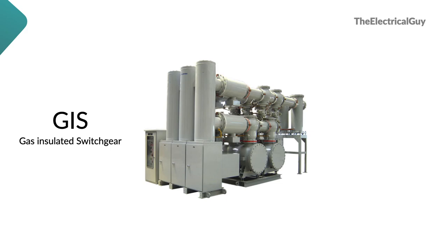There are different compartments given. The circuit breaker will have a separate compartment. The current transformer will have a separate compartment. The voltage transformer will have a separate compartment. And everything is insulated by SF6 gas. As you can imagine, this is safer than the AIS substation or AIS switchgear. So this is a GIS.